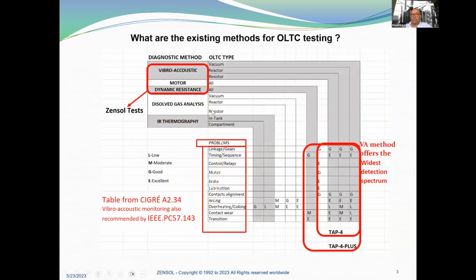What are the existing methods for OLTC testing? So we have 5 methods: the Vibro-Acoustic, the motor current, the dynamic resistance, the dissolved gas analysis, and the thermography. And the Zensol is able to do these 3 tests in one instrument. And this is the kind of problems that you can detect when you have linkage gears, timing sequence, control relays, motor, brake, lubrication, alignments, arcing, overheating, contactor, and transition.